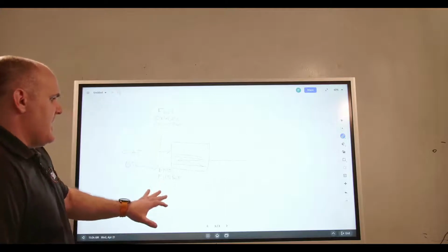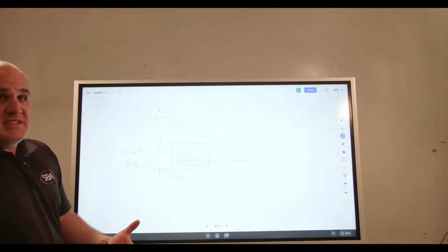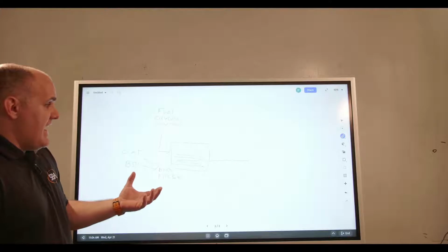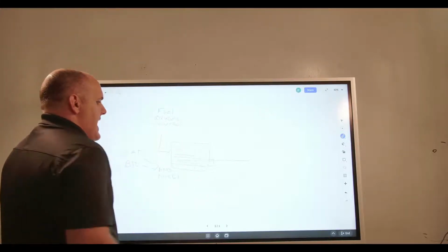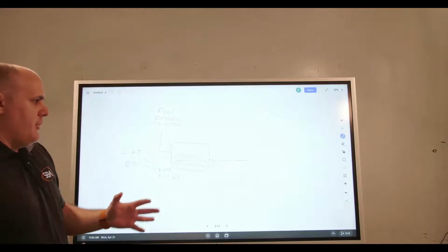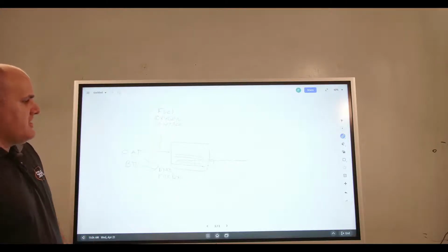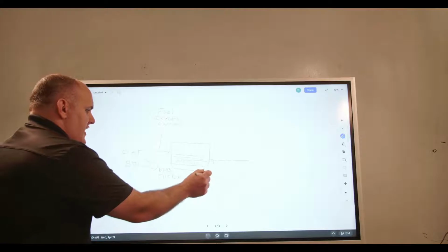And then once this enable triggers, that's typically like a RIB U1C relay that is connected to the control panel, typically sitting at the front of the boiler, and that RIB U1C will enable the boiler. Now, we also have the opportunity to vary the fire rate.